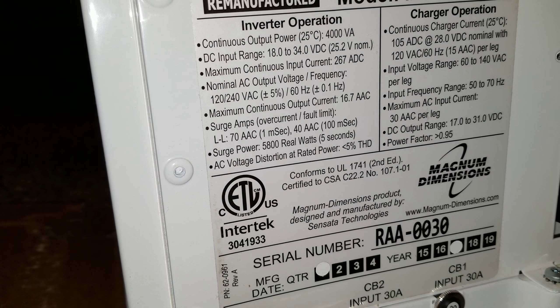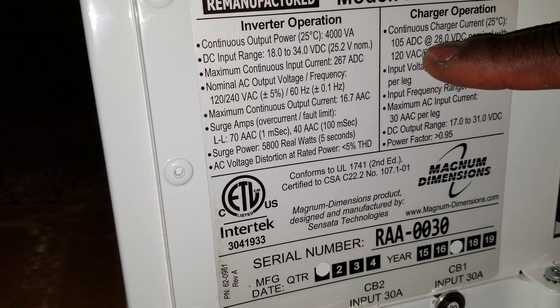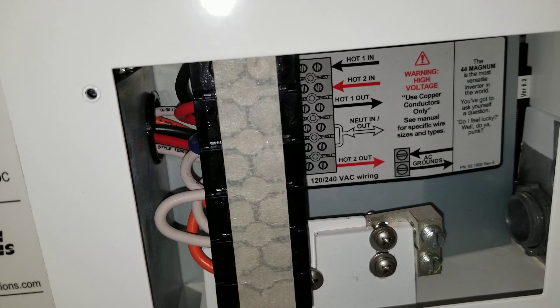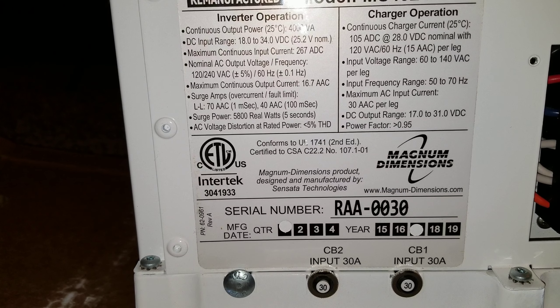This is going to give you 240V power - 120 to 240, leg one and leg two. It takes in from 18V all the way to 34V range for 24 volt. Nominal voltage is 25.2V at 25 degrees C. You're gonna see 4,000 volt-amp right there - 105 AC amps DC at 28V nominal. You see leg one, leg two, hot, neutral, and ground.